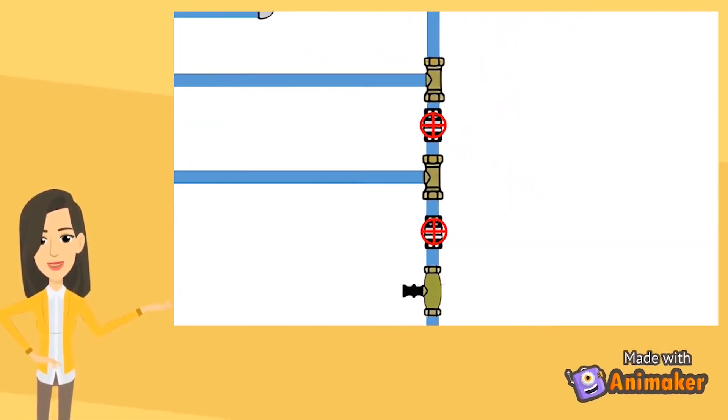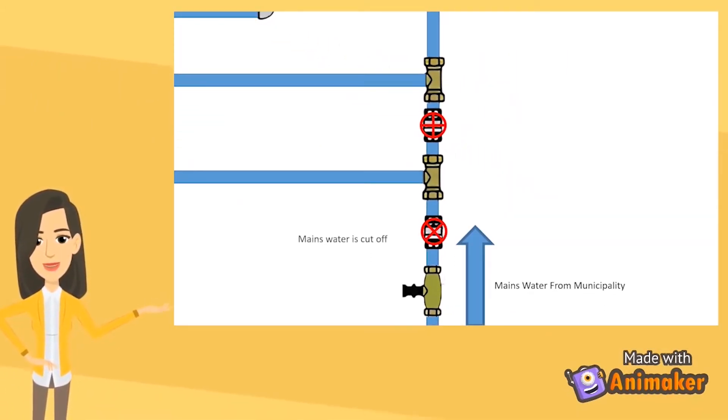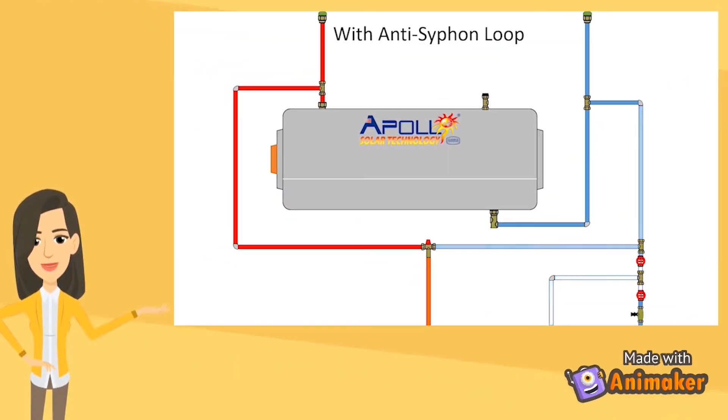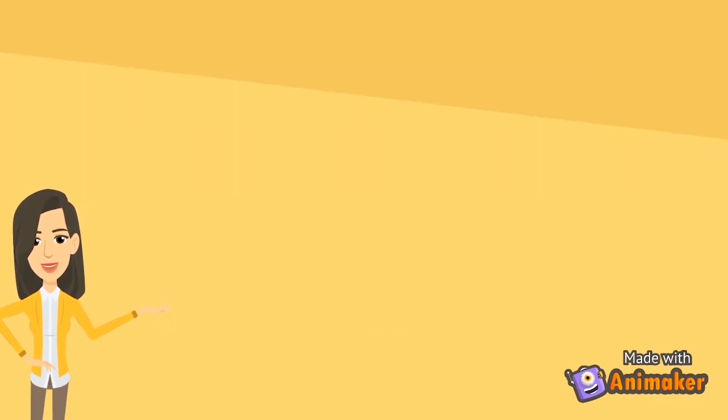Hence, when a plumber installs an anti-siphon loop on a geyser above the cold water inlet, the hot water inside the geyser cannot drain out through the cold water inlet pipe, as it is impossible for water to naturally flow upwards and above the water level inside of the cylinder. The vacuum breaker is at the topmost part of the loop to function as the open end of the hose, thus preventing the siphon process from occurring.